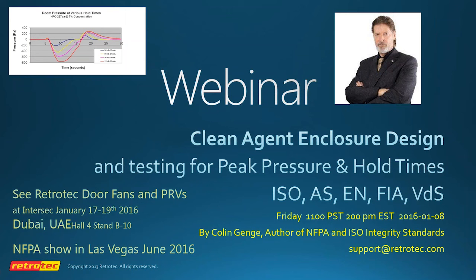Now, a question by David asking, will peak pressure affect the hold time? They're not directly related. They are related from the simple point of view that the hole in the enclosure affects the hold time, and the hole in the enclosure affects the peak pressure. But a large pressure spike doesn't really affect the hold time much at all. So if you have a 100 Pascal pressure spike or a 1000 Pascal pressure spike, that pressure doesn't change anything to do with the hold time.